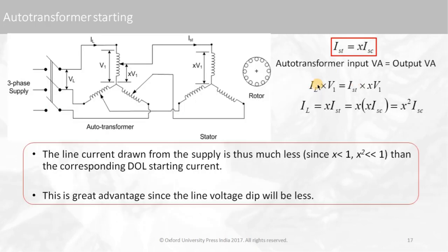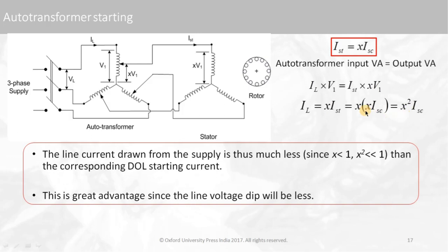Since in a transformer the input volt-amperes equal the output volt-amperes, for the auto transformer: input current is I_L at voltage V₁, and output voltage is x·V₁ at current I_start. Therefore I_L · V₁ = I_start · x·V₁, so V₁ cancels and I_L = x · I_start. Since I_start = x · I_sc, it becomes I_L = x² · I_sc.